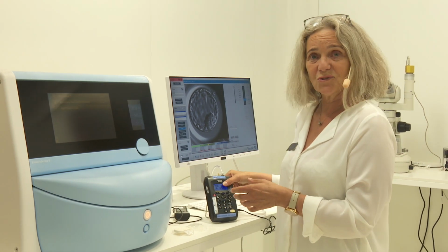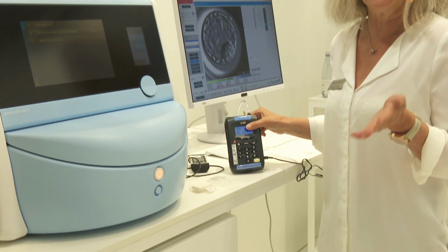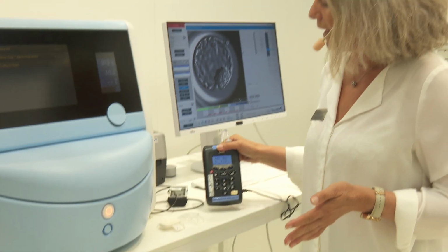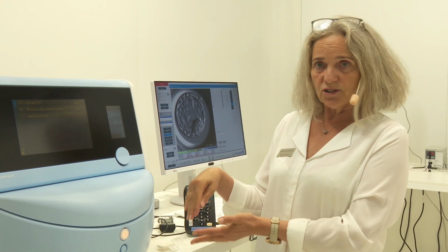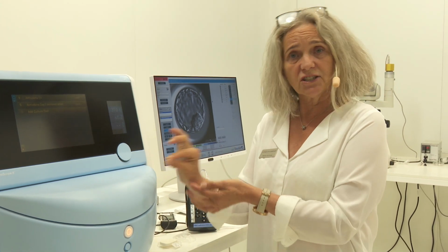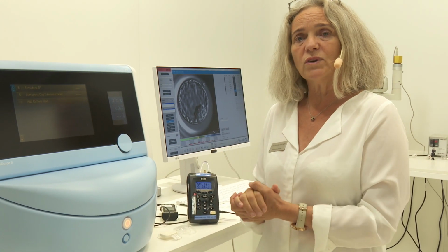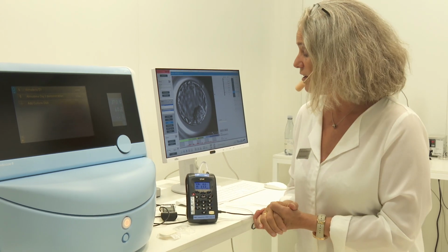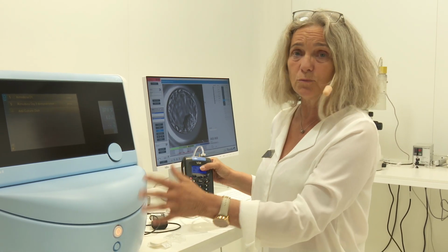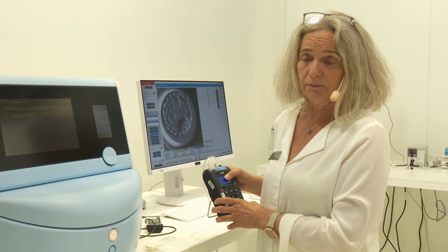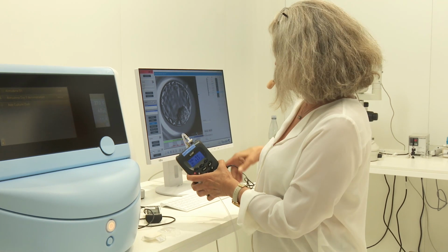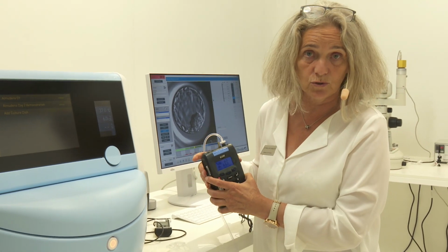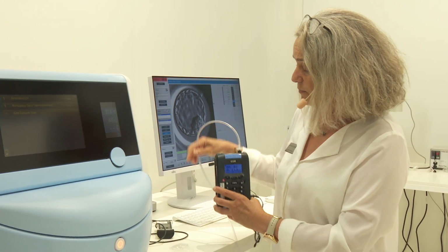So before you start doing validation and calibration of the internal sensor of gases and temperature, you should use, of course, your gas analyzers, and they must also be calibrated before use. So when you do a validation of the temperature, you need to open up the instrument for inserting a probe. So always start validation of the gases, because then you haven't opened it and it is completely stable. The gas analyzer should be fully charged or be on mains supply when you do it. Good. So what you do?